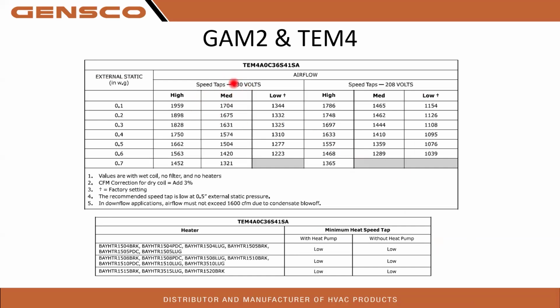Speed taps, you got your 230 volts. You got medium, high, or low. At a 0.5, you're running about 1504. So again, you're going to be changing out your speed taps on your air handlers. Again, that's minimum heat speed tap without heat pump, with heat pump.